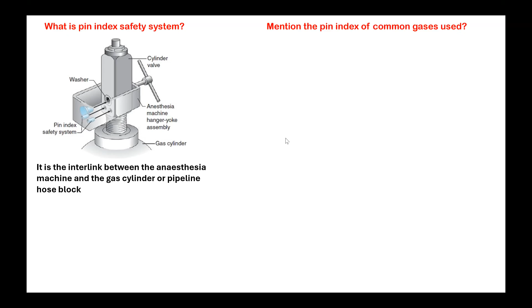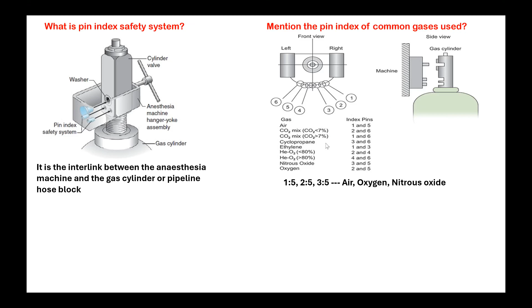The pins are placed as though they are placed on the face of a clock. So one position, two position, three position like that. For air, the pins will be in one position and five position. For oxygen, it will be two position and five. And for nitrous oxide, it's three and five. So that means the pin will come closer to nitrous oxide, and it will be farther away for air. That is how we remember that.